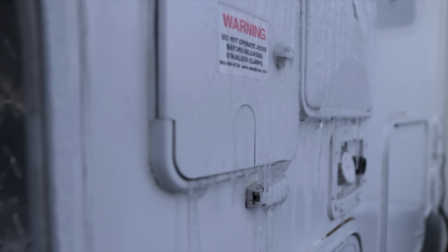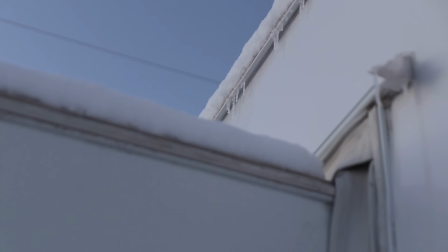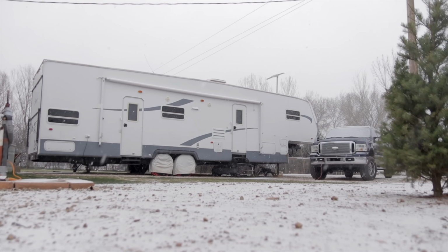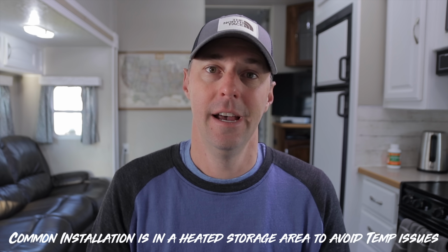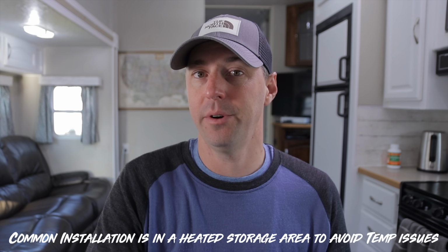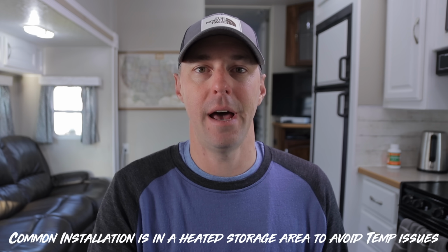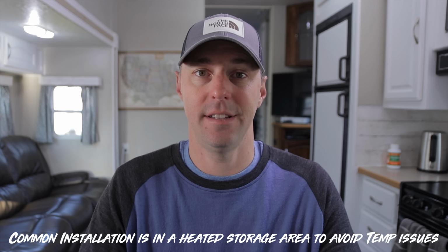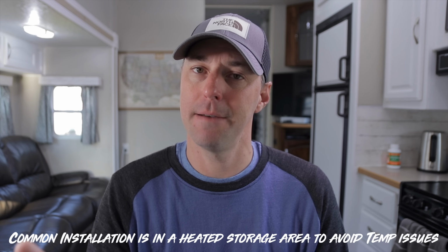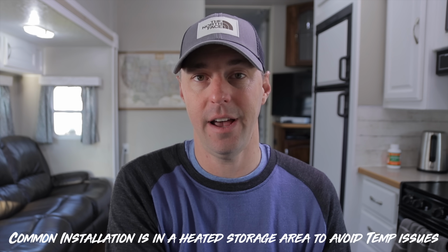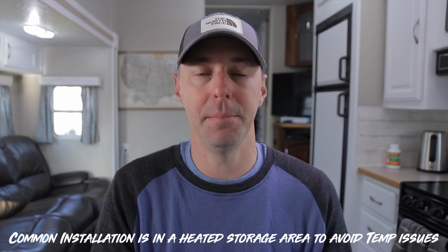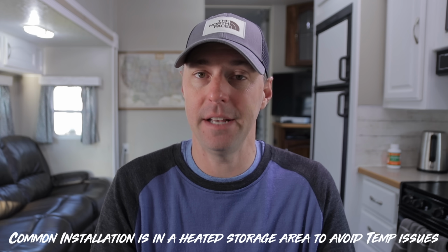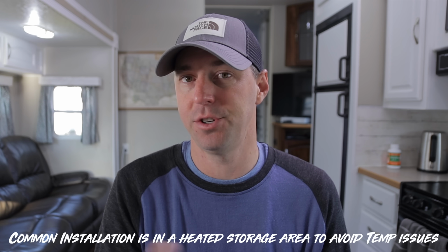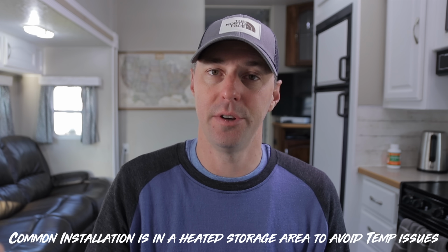Now, if you're somewhere that's extremely cold in winters, it does have a limit. That is where you can use the battery, but as far as charging the battery, it can't be below 24 degrees. That's what the Battle Born battery BMS device has programmed into it. Anything below 24 degrees Fahrenheit will be bad for the battery and you'll be doing damage to it. So the BMS protects it and it just won't accept a charge. You have to warm up that battery so you can start charging it.